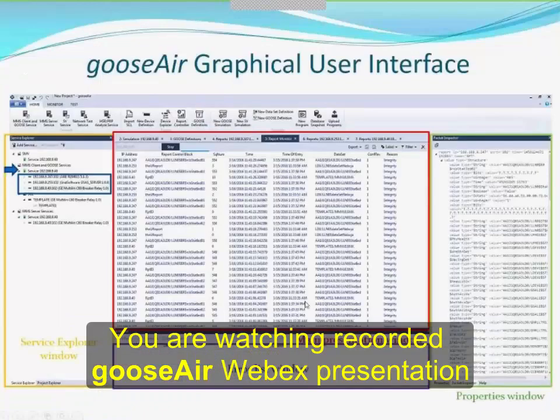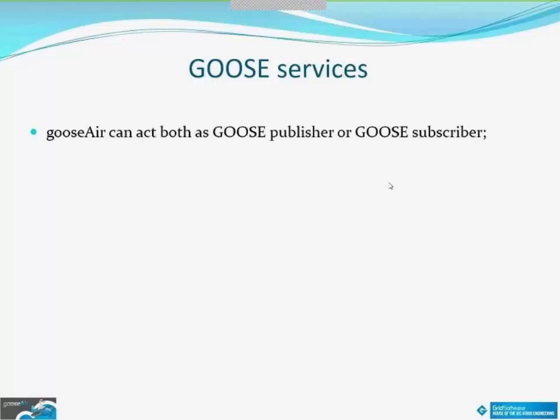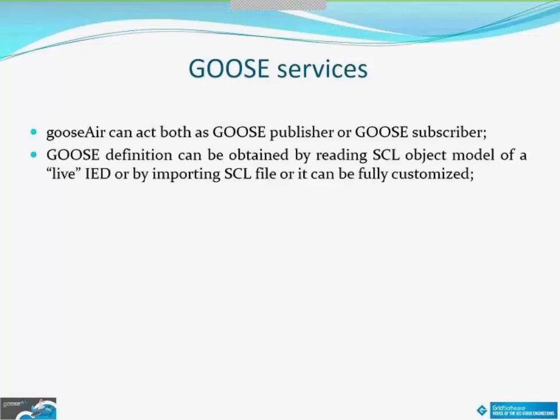So you can continue with the presentation. Now I'm going to show you the gooseAir assessment chart supported by gooseAir. GooseAir is able to simulate goose messages, monitor goose traffic, or even subscribe in a way to a specific goose message. When it comes to simulating goose messages, goose definitions can be obtained either by reading goose definition from a library, or by importing an SCL file as I have done previously.